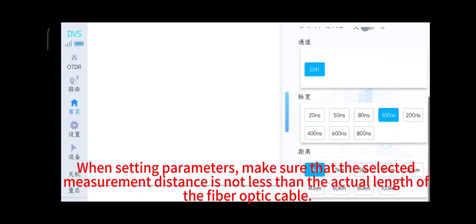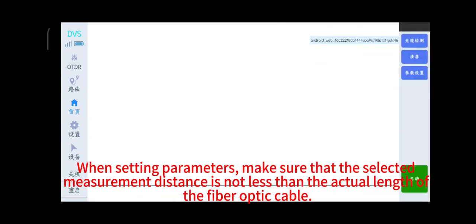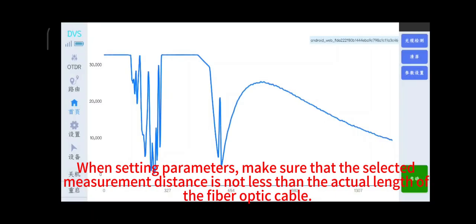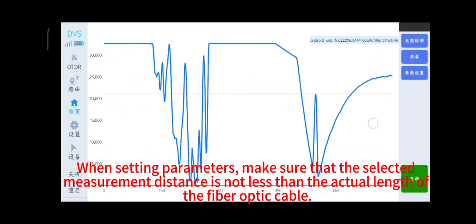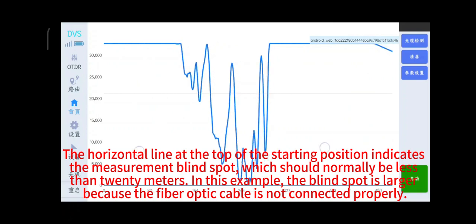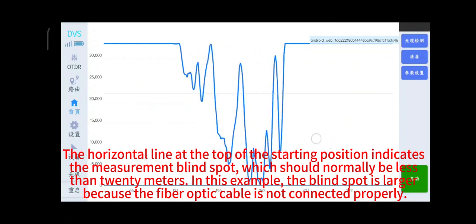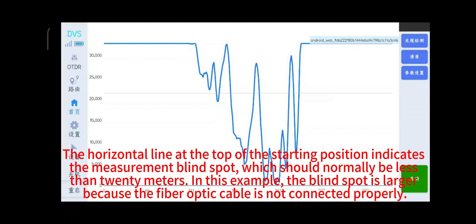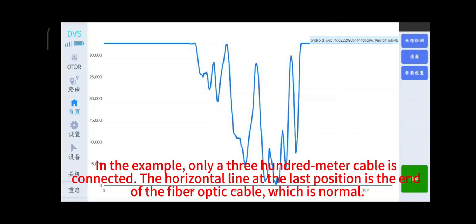When setting parameters, make sure that the selected measurement distance is not less than the actual length of the fiber optic cable. The horizontal line at the top of the starting position indicates the measurement blind spot, which should normally be less than 20 meters. In this example, the blind spot is larger because the fiber optic cable is not connected properly. In the example, only a 300-meter cable is connected. The horizontal line at the last position is the end of the fiber optic cable, which is normal.